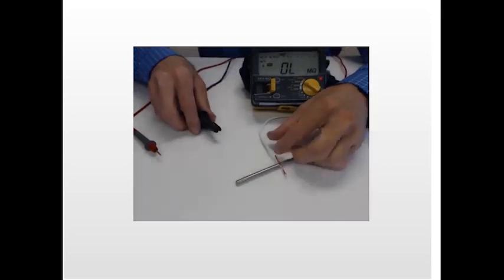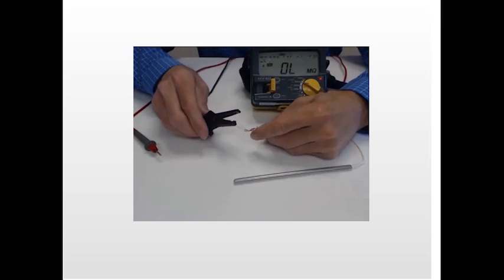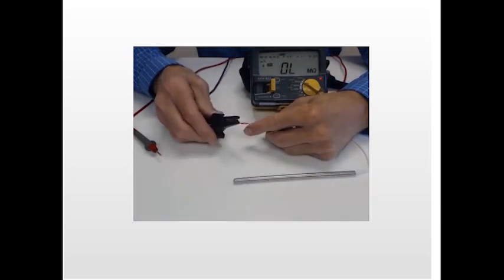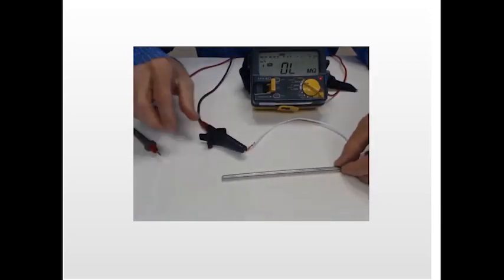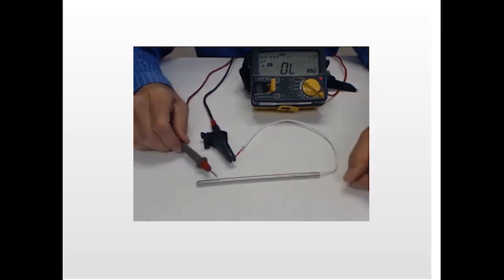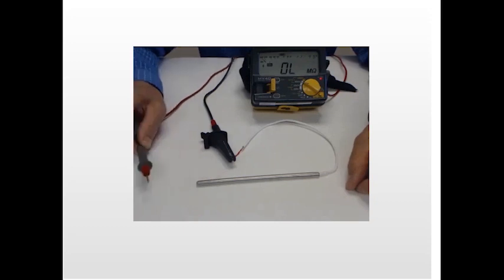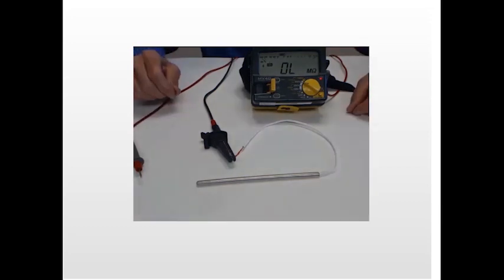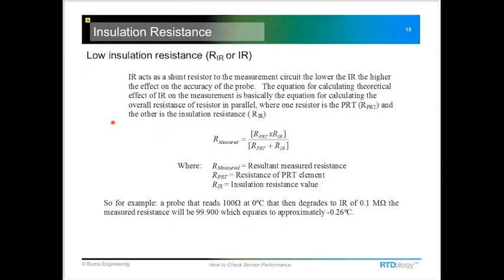And now this probe is a little different, and this one we'll check, and this one should check out fine. So here we're not getting any reading. It's kind of an infinite reading here, where it's over the capability of the meter to measure it even. So this one we would consider as a very good probe.